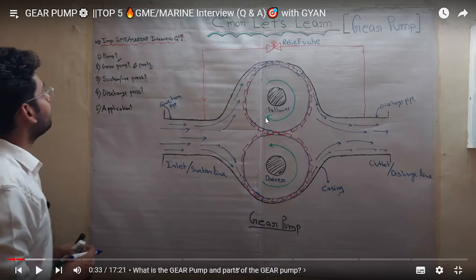Tell me — other than driver and follower gear, what else do you see in the gear pump? A student mentioned the relief valve. You see a relief valve in gear pump, but not in centrifugal pump. What is the reason for not having a relief valve in a rotodynamic pump but having one in a positive displacement pump?